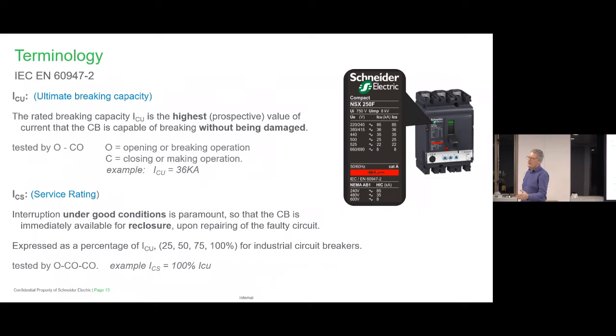Yes, that's right. It is an application-based thing, and some protection devices are going to see more action than others, and some will sit there for years and nothing ever happens. But the main thing I would say to everybody is, please open and close the breaker once a year, or once every couple of years. Please do that at least. It should be written down somewhere, part of the maintenance program, because you never know when that time is going to come. You want it to operate.